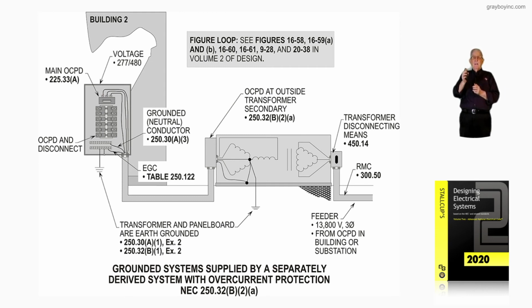We've already talked about the overcurrent device outside at the transformer in accordance with 250.32(B)(2) little a. We have a disconnect there at the transformer in accordance with 450.14, and we've pretty well covered the rules of the figure 16-57 that comply with NEC 250.32(B)(2)(a). Notice the mains now. The number of mains to this building are sized by 225.33(A), and the number permitted there, 6 or less. And then do not forget 225.32 exception 1, because you may want to use that, and use it in conjunction with 250.71(B) 1 through 4, and talk to the authority having jurisdiction, so we're all on the same page when you're getting a final on your design and installation, as illustrated in this figure 16-57.